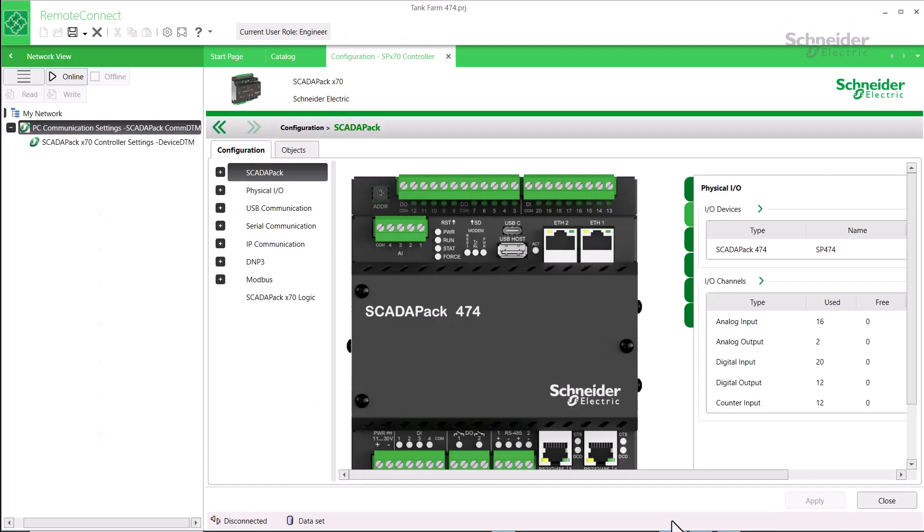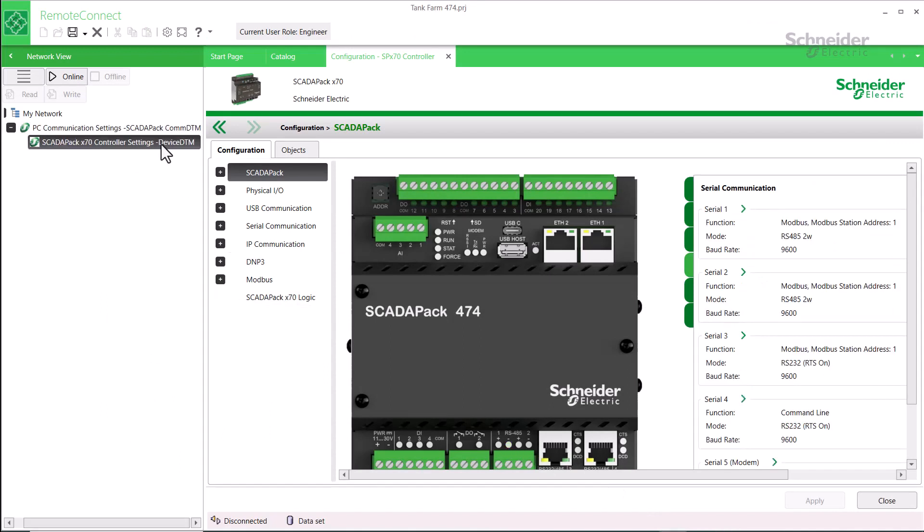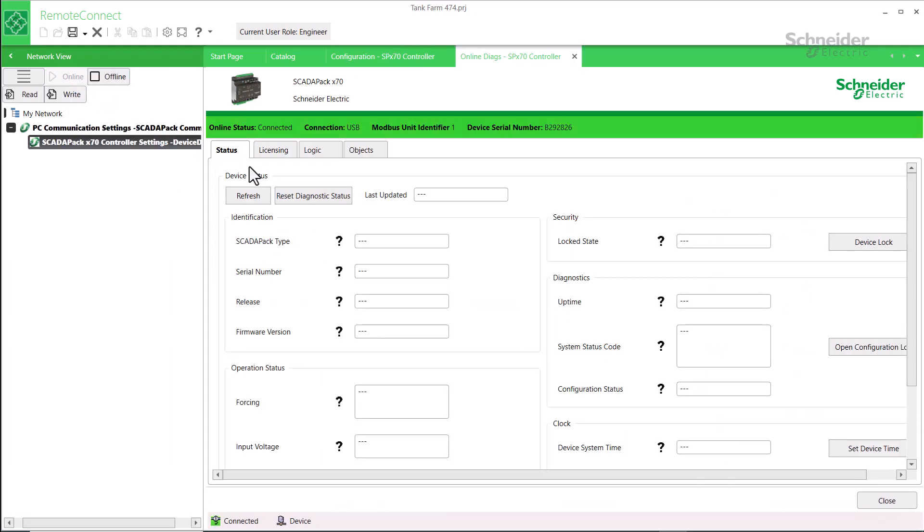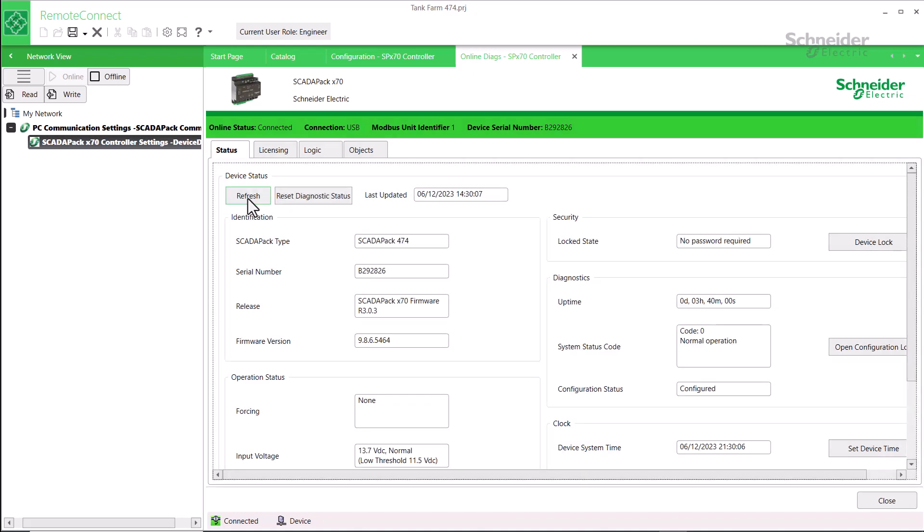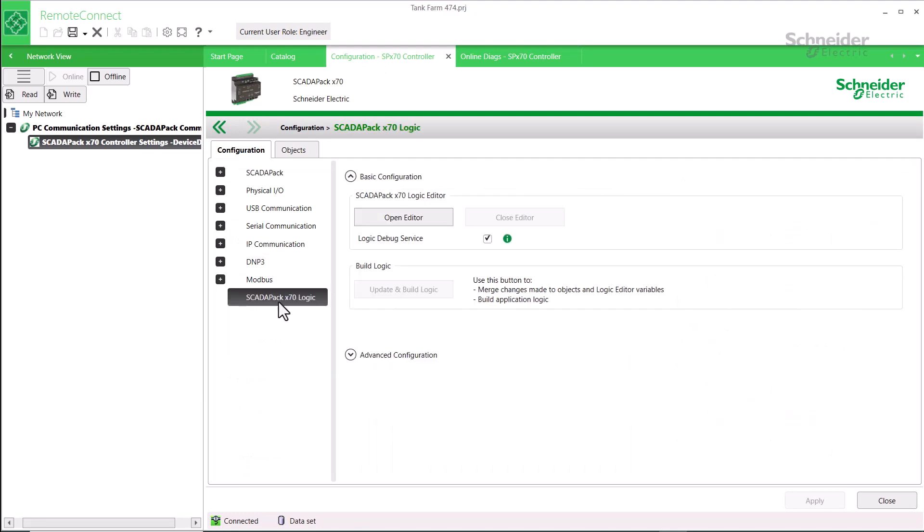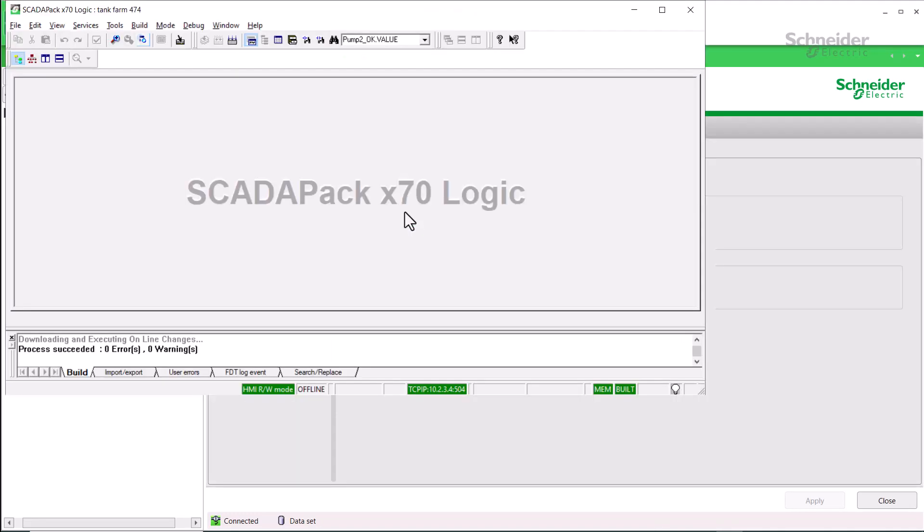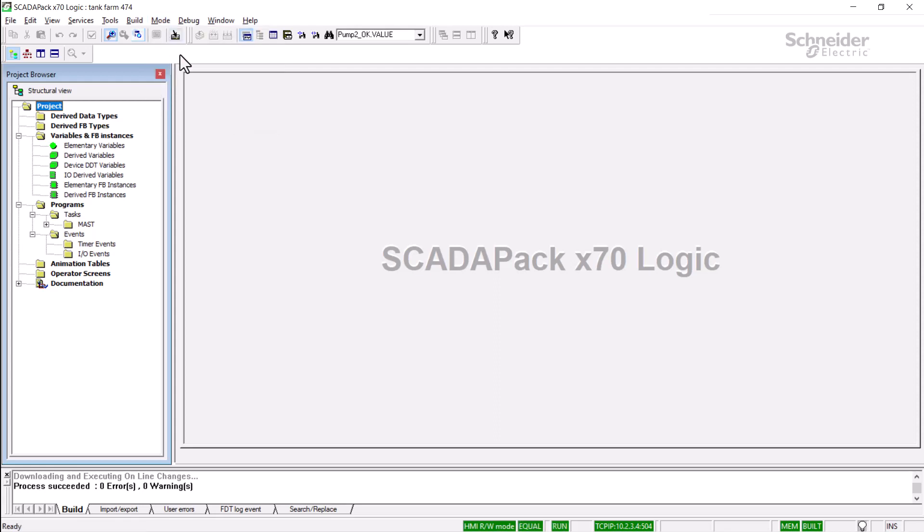Now let's go through the procedure in RemoteConnect itself. First, I'll go online with RemoteConnect. I'm connected to a SCADAPack 474 via USB. Once online, we can see that the status bar indeed does not display 'different', so we're OK there. Now I'll open Logic Editor by going to the configuration tab, SCADAPack x70 logic and click open editor. I'll go online here by selecting the mode menu and connect. Now that we're connected, we can see that the status bar states 'equal', so we're ready to proceed.